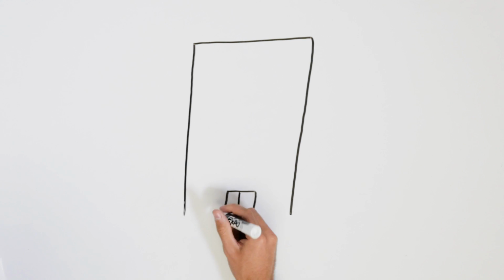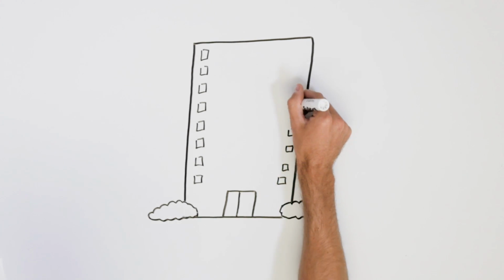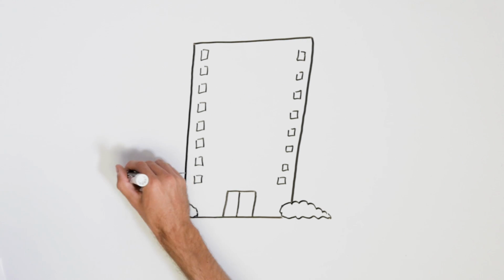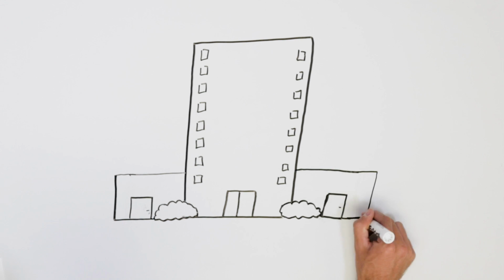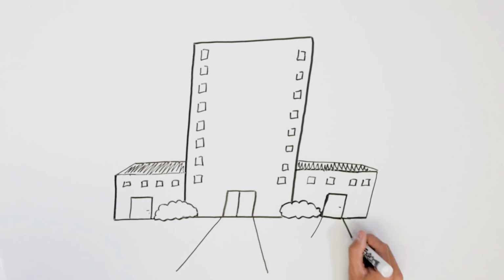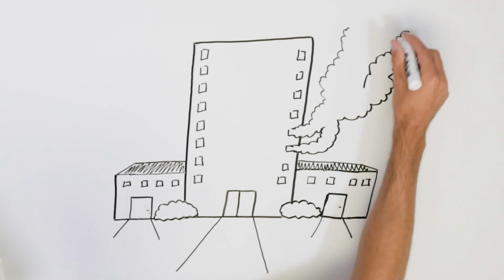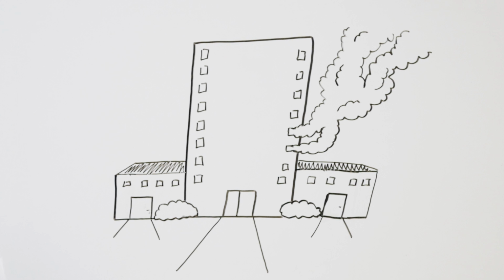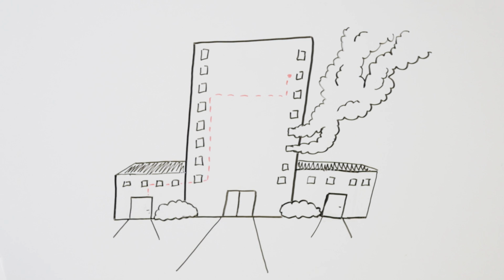Most stairwells in commercial and institutional buildings are designed to protect the means of egress using fire-resistant construction and fire door assemblies as opening protectives. When building occupants are within a stair enclosure during a fire, the stairwell is intended to provide a safe pathway to the exit discharge. During a fire, a stairwell could become compromised by smoke and may no longer provide a safe means of egress. If this happens, building occupants must be allowed to leave the stairwell and re-enter the building to seek refuge or find another exit.